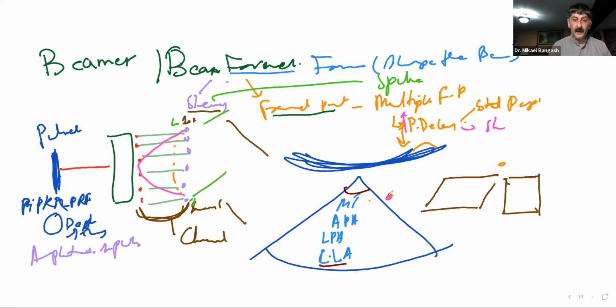Whereas, on the other hand, if you want to just focus at a deep point, we move the focal point from a shallow location to a deeper location. That's actually going to send a command to your beamformer and say, well, you know what, buddy, you need to reduce the phase delay. Did you guys get that?